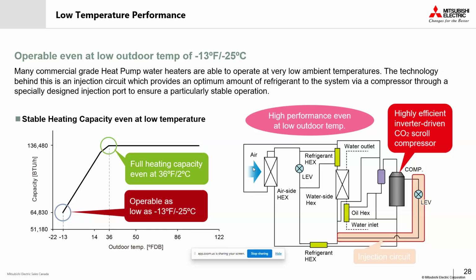And as you see here, for this operating curve for this particular machine that we're looking at, you can see that we're still able to achieve full capacity down as low as 2 degrees Celsius. So I think this is an answer to a lot of those common misconceptions out there.